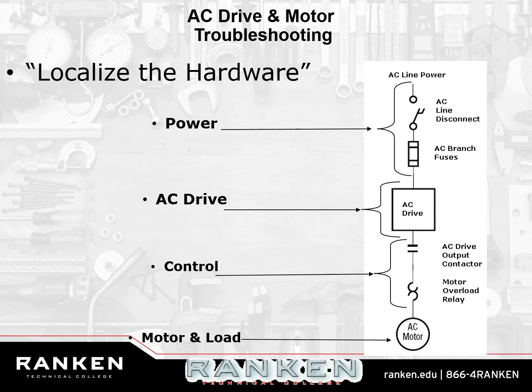So you localize the power. Localizing the power means just figuring out which one could be the culprit. It's got to be one of these, if this is the only thing that comes from the pole, right? If this is what's coming from the power source, from the transformer or the pole, the only thing it could be is one of these things.